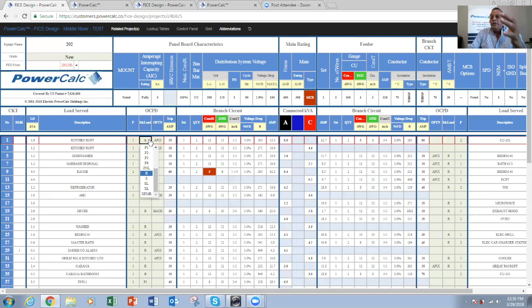You have to keep track of these three in order to be able to apply the demand loads. And you have to keep them separate, otherwise the job of applying demand load becomes very tedious. What I found is that most engineers don't really separate these types of loads, they just input them together, connect everything together, because they are not going to apply any demand load. That turns out to make your system way over designed and very costly.